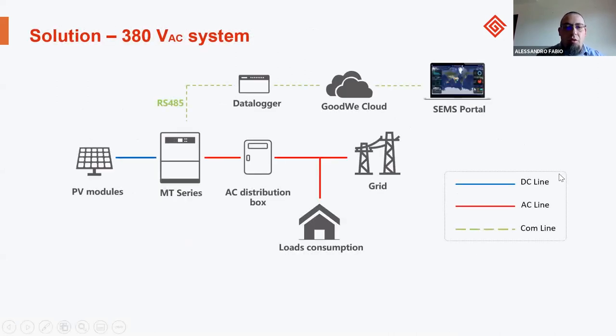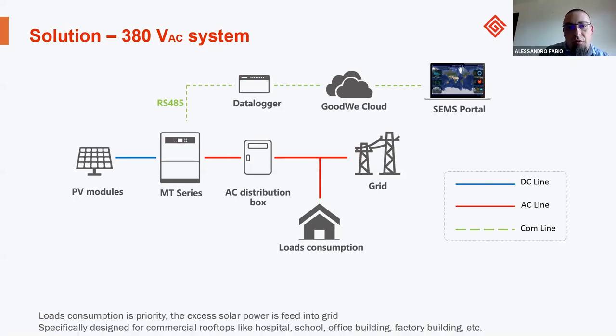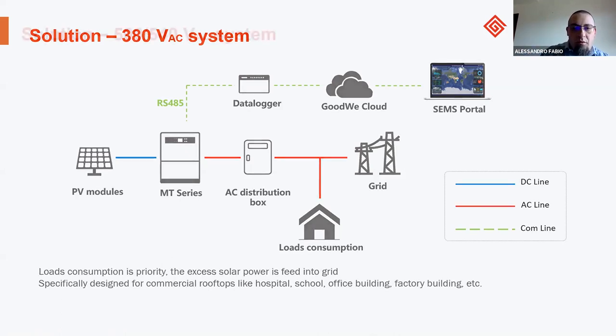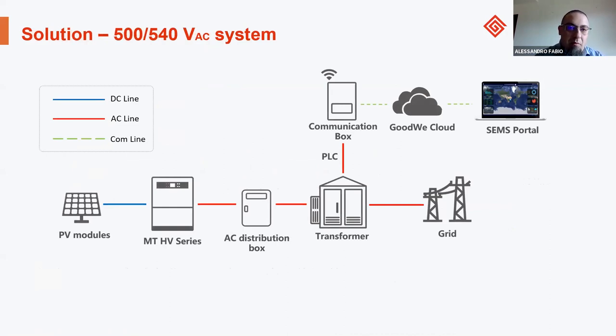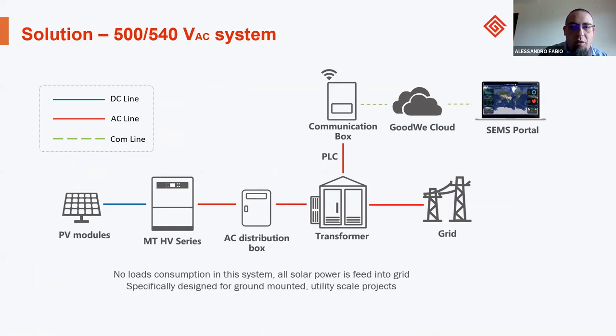So I show you schematic diagrams, not for utility scale in this case, but for industrial connection, where, for example, self consumption is possible. So the MT series has this possibility for big rooftops, for example, and you can produce self-consumption energy and at the same time put energy to the grid. The second solution, for example, is with the transformer. It's more of a utility scale solution with 500 or 540 volts AC, with transformer, where in this case you cannot do self consumption because there are no loads on site.